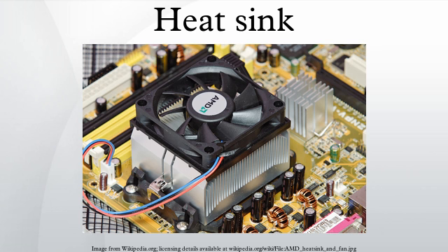Consider a heat sink in a duct, where air flows through the duct, as shown in Figure 2. It is assumed that the heat sink base is higher in temperature than the air. Applying the conservation of energy, for steady-state conditions, and Newton's law of cooling to the temperature nodes shown in Figure 2 gives the following set of equations. Where using the mean air temperature is an assumption that is valid for relatively short heat sinks. When compact heat exchangers are calculated, the logarithmic mean air temperature is used. Here, m-dot is the air mass flow rate in kg per second.